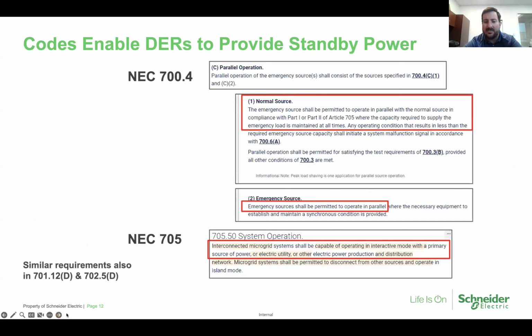Now, where exactly does the parallel operation come into play? Well, we see it referenced in numerous other parts of the code where it basically says very similar phrasing. The emergency source shall be permitted to operate in parallel with the normal source. If we go down another one, the emergency source shall be permitted to operate in parallel. Again, pretty much the same phrasing. One step below that, interconnected microgrid systems shall be capable of operating in interactive mode, which is just a fancier way to basically say what it says in the top two as well, which is you could have your sources work in parallel with the utility when everything's okay.